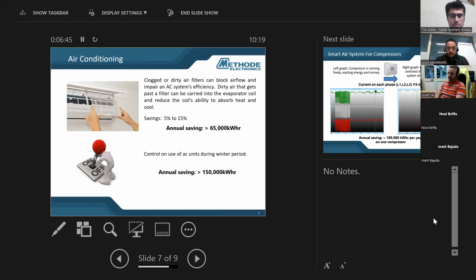Also, especially during the winter period, we are controlling the use of AC units. For example, if we have AC units in the electrical switch rooms or the hub rooms, we try to switch them off, because the temperature is quite good during those periods. There are also some areas where we control the use and switch off some compressors of the AC units. Although we maintain a decent temperature, we avoid waste when it comes to AC units. By this, we calculate a roughly annual saving of 150,000 kilowatt hours.